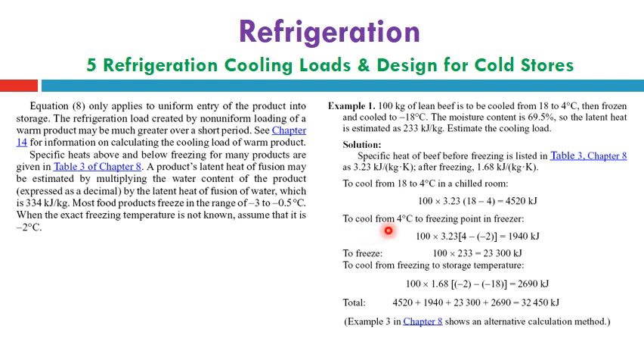Q4, to cool from 4 to the freezing point in the freezer. The same mass multiplied by the Cp, from 4 minus -2, is equal to 1940 kilojoule. So finally, the latent heat to be removed in the freezing process: 100 kilogram multiplied by the latent heat considered based on the water content, 233. So we can get 23,300 kilojoule. Then to cool from freezing to storage temperature is the final part.